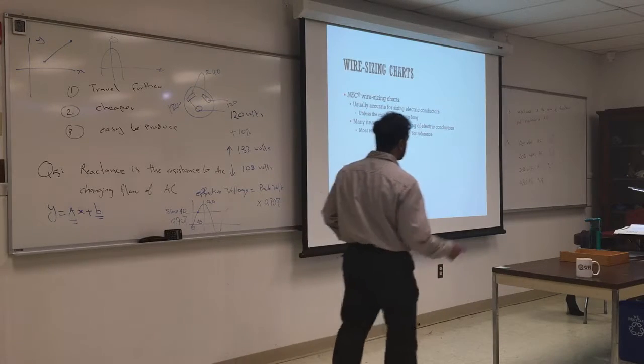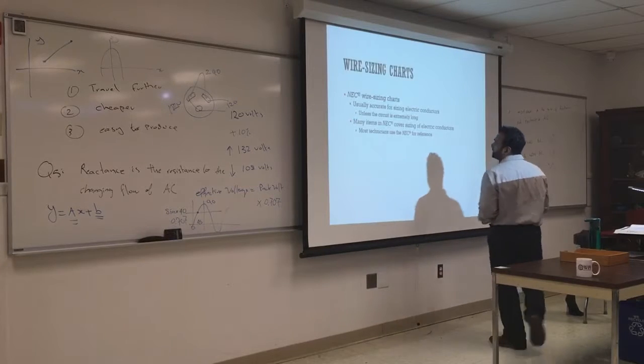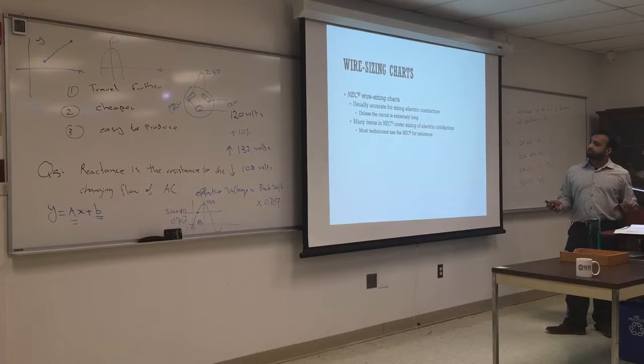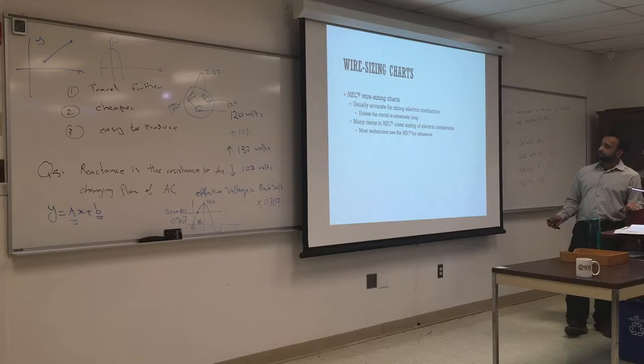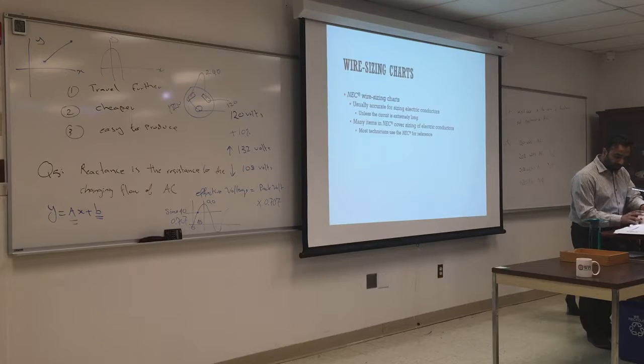So wire sizing charts, we can look at it. They're accurate for sizing electrical conductors unless the circuit is extremely long. What is extremely long? That should be on the nameplate. They'll tell you from the source this equipment should not exceed 100 yards. Again, NEC is the national code, and that's what we go by, and then we'll go through the book here so you can look at it, or have an idea of what we're talking about.